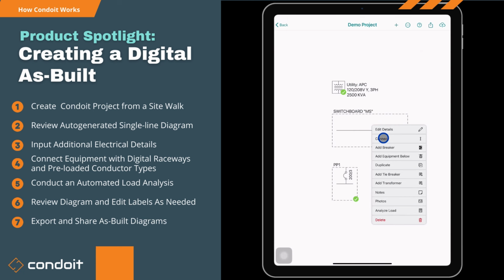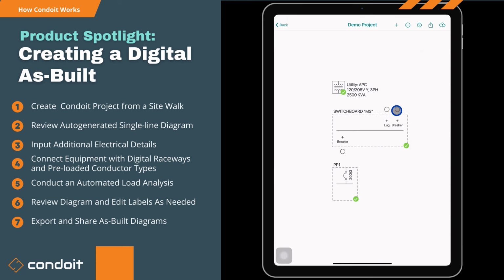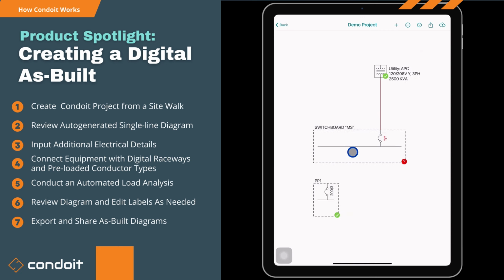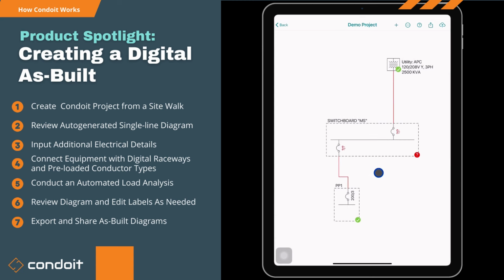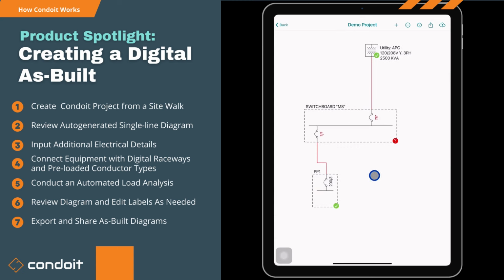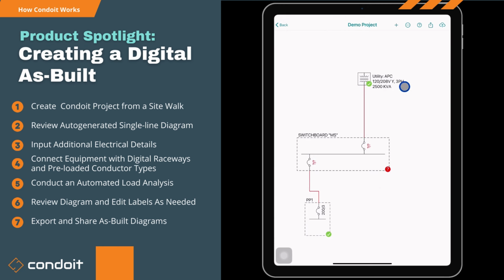But the first thing we're going to do is hit connect here. And it's going to say, well, how do you want to connect it? We're going to connect it with a main breaker upstream to this utility connection. Tap that, it's going to draw us a raceway. And then we'll also connect it downstream to this little panel that we just put in here, panel PP1. That's going to add a breaker and connect us to that main breaker going into panel PP1. But we're missing information. So these raceways know that they're there, but they don't know what's in them.